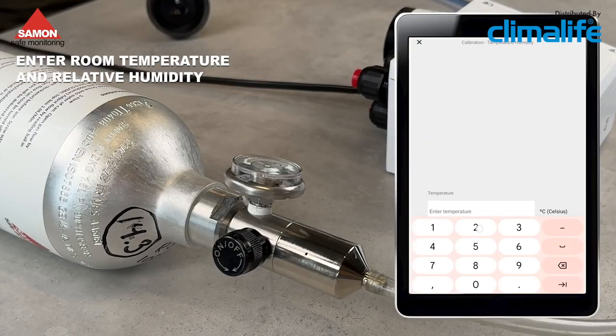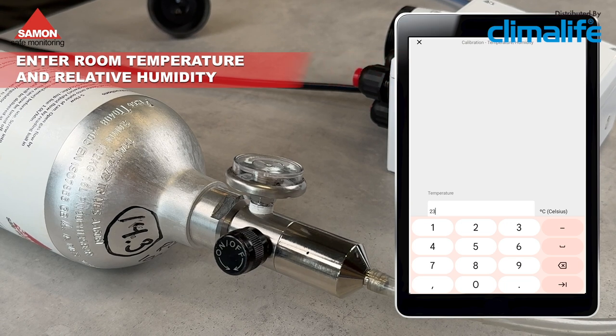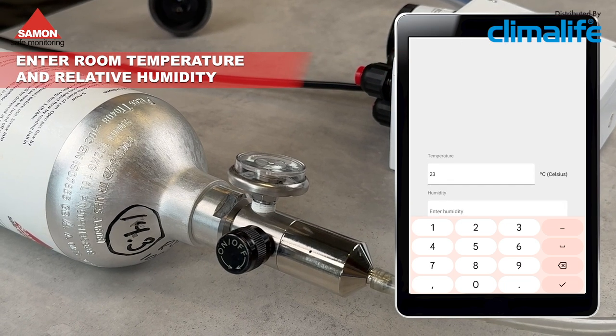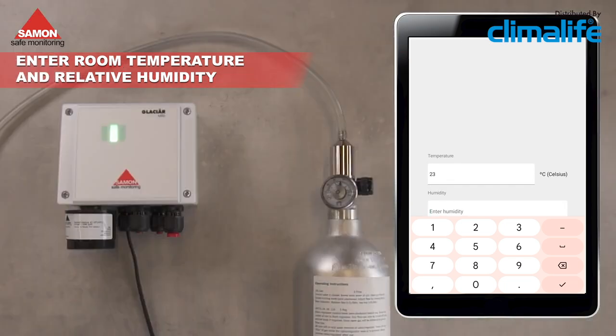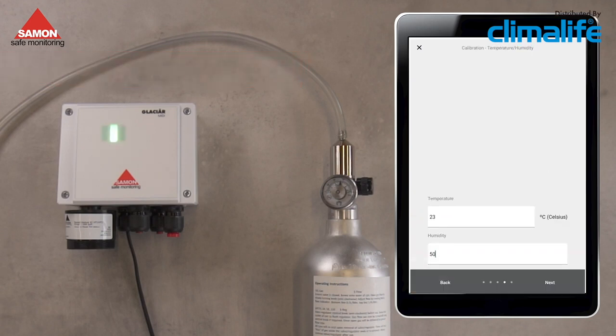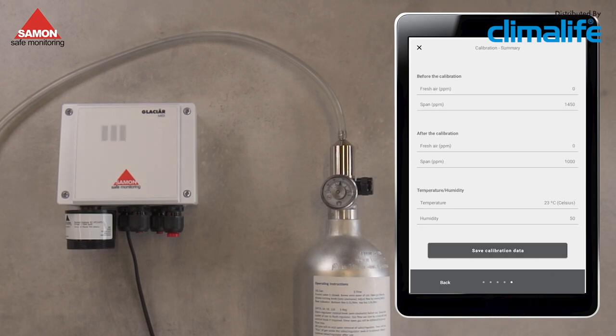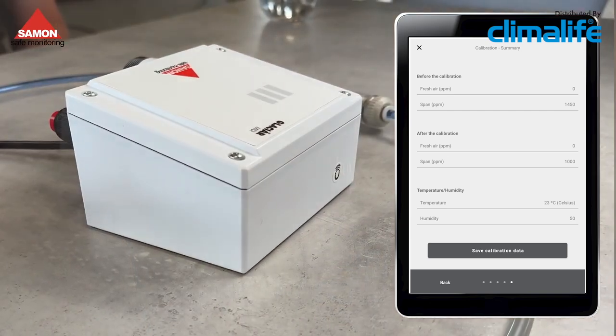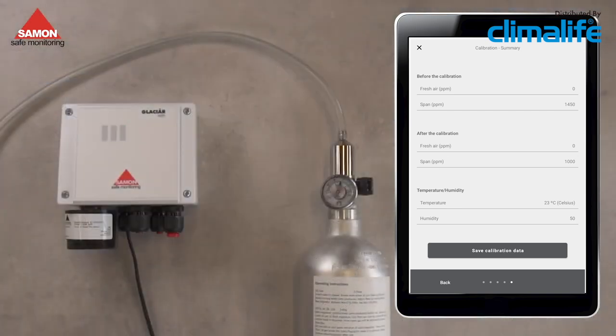Enter the room temperature and relative humidity. These values will be entered on the calibration certificate to indicate the environmental conditions during calibration. It is not necessary to use a calibrated instrument to perform this measurement. An indicative value is sufficient. Verify the summary screen, checking that all the information has been entered correctly before generating the calibration report.